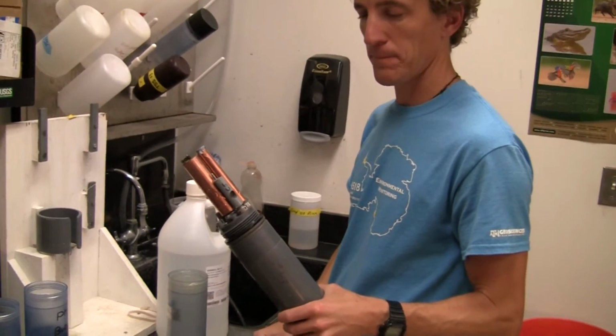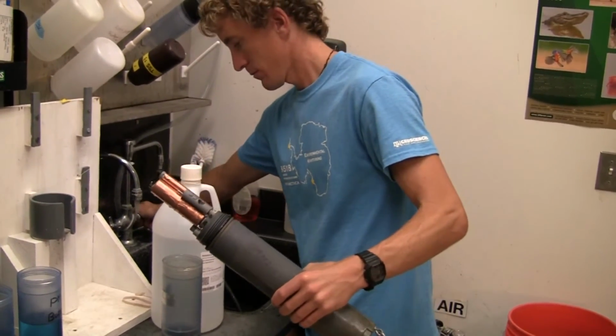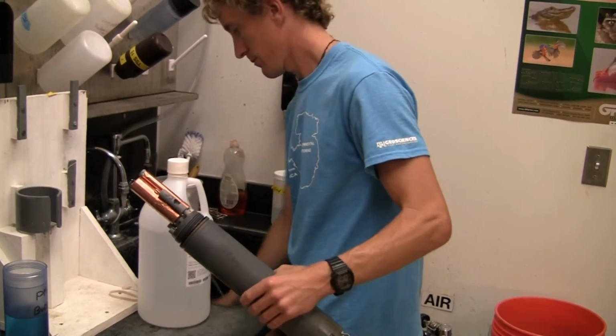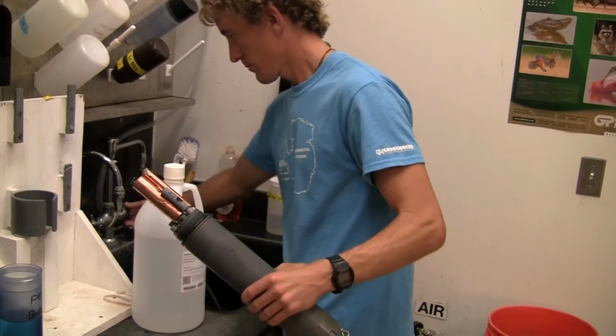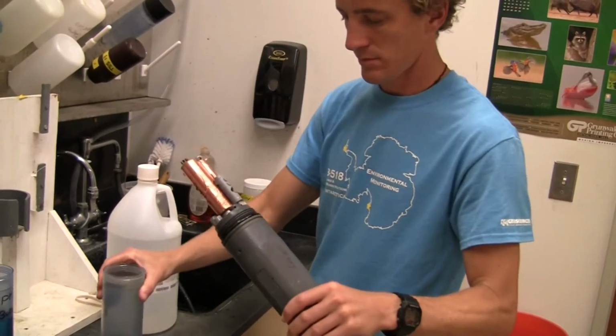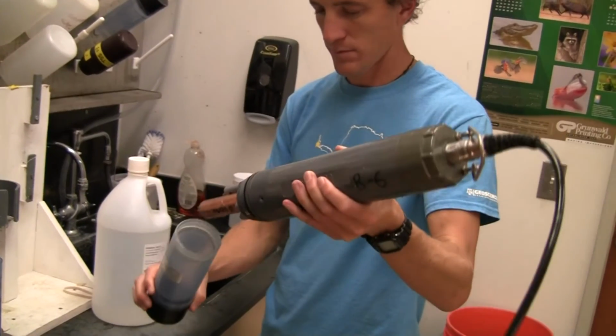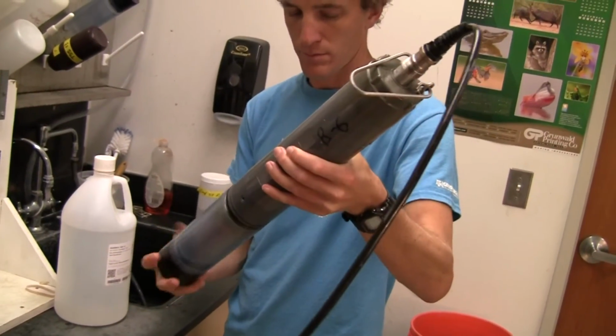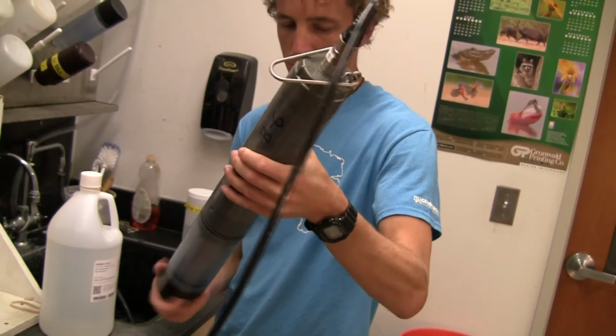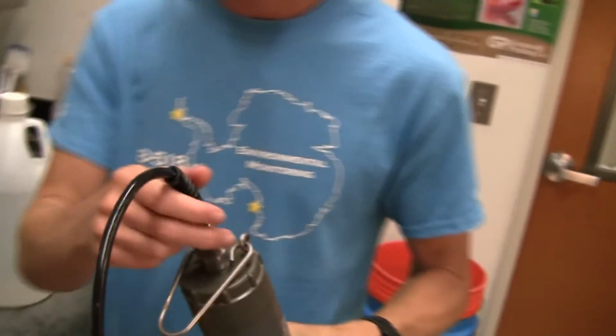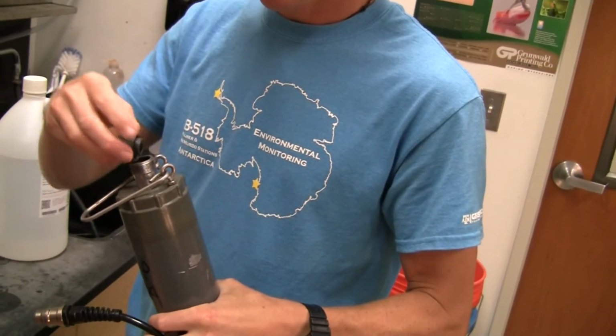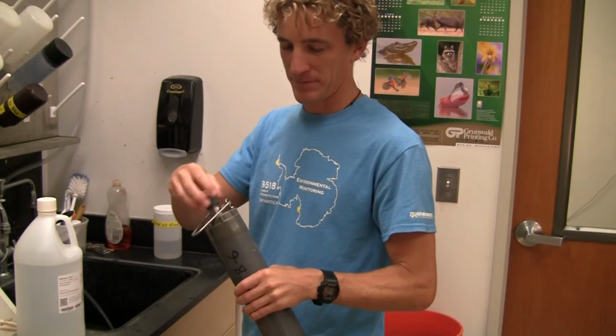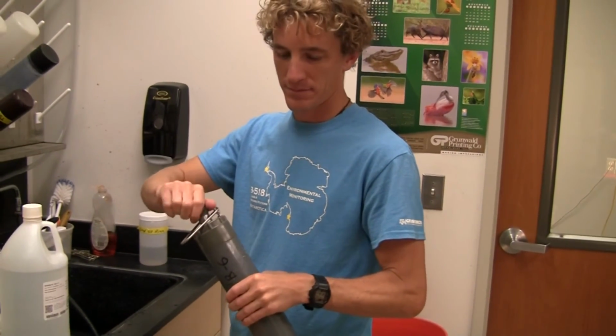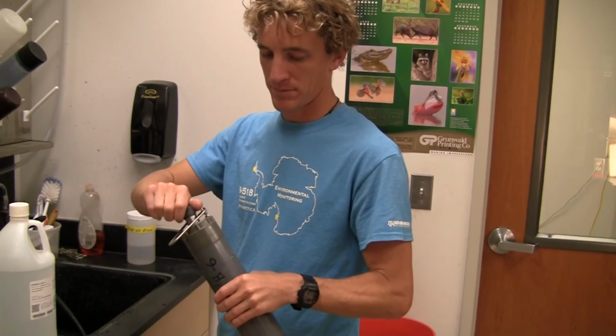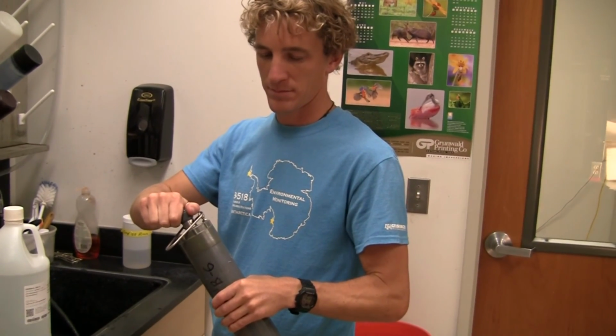So the way to store this unit is you put just plain tap water into the storage jar, because the sensors have to stay wet. You screw the sonde into the cup. Disconnect from the computer and place the cap that goes to the corresponding sonde back on. So now we've calibrated this unit and are ready to store it on the shelf. This unit is ready for discrete measurements. And in the next video, we'll talk about the deployment procedures to deploy this in the field.